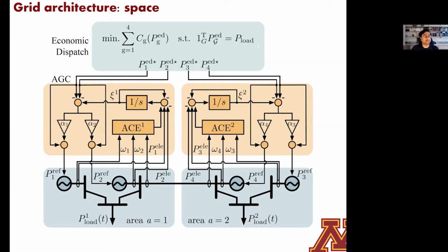Okay, and this is done in a rolling 5 to 10 minute horizon. So this estimate of the net load, which is going to be the sum of both of these loads at the very bottom here, is already outdated by the time you solve this problem, but that's fine. We solve this problem. We get these optimizers, but then these are not exactly the real power that the generators are going to produce. You run them through this cruise control, this real-time feedback control mechanism.